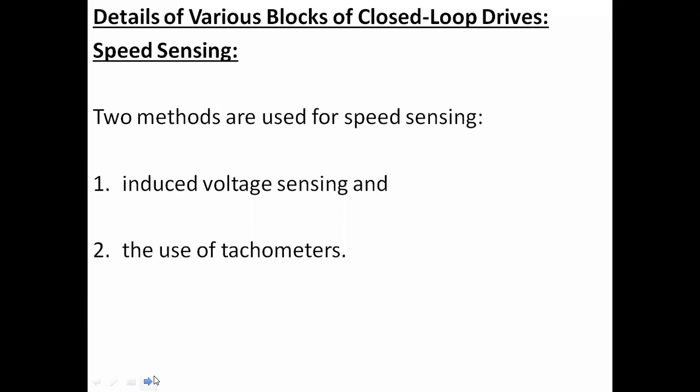So now speed, first one: the speed will be proportional to back EMF at a constant speed, right? So if field control is not used, then speed can be sensed by measuring the back EMF, nothing but E = VA - IARA.